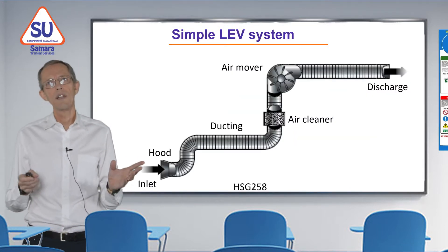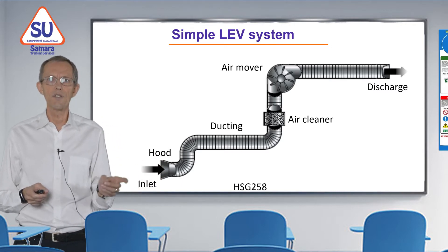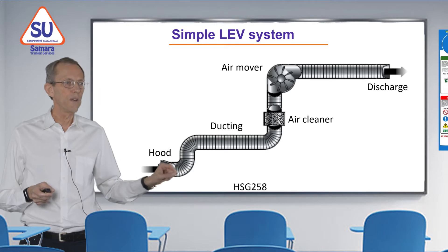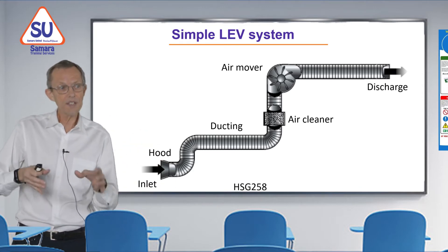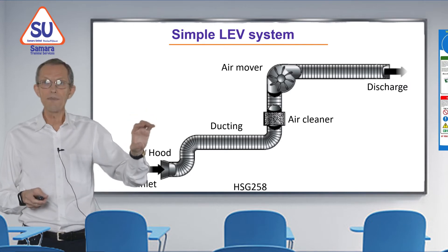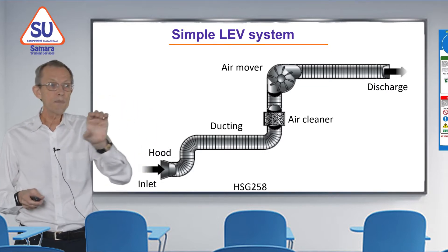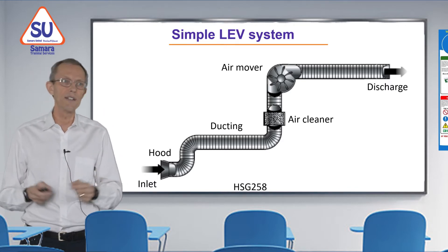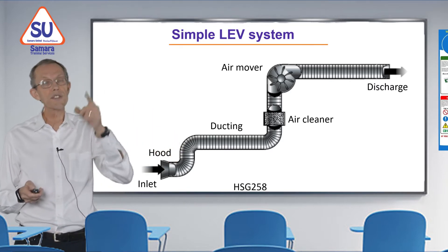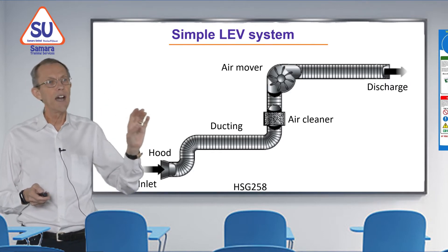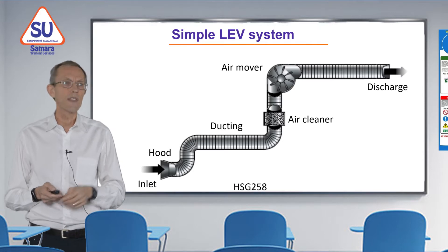This is a simple local exhaust ventilation system diagram, taken from Health and Safety Guidance Note 258. At the bottom we have the inlet — the hood — the place where we're sucking air with the fumes or dust into our system. Once it's in the system, coming through the hood, the contaminant gets sucked up through the ducting, through bends or straight pipes, and then into an air cleaner, which is usually a filter. Then we have something to move the air — a fan — driving the air. After it's been driven through the filter and cleaned, we discharge it in an appropriate place.